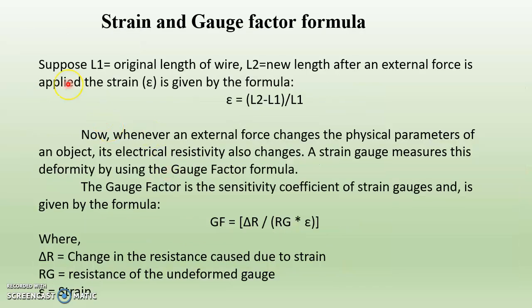Now what is the formula for strain and gauge factor? L1 is the original length of wire and L2 is the new length after an external force is applied. So strain is given by L2 minus L1, divided by L1. Whenever an external force changes the physical parameter of an object, its electrical resistivity also changes. The strain gauge measures this deformity using the gauge factor formula. The gauge factor is the sensitivity coefficient of strain gauges, given by delta R, the change in resistance, divided by Rg, the resistance of the undeformed gauge, and epsilon, the strain. Using this formula we can calculate strain and gauge factor. This is called strain.